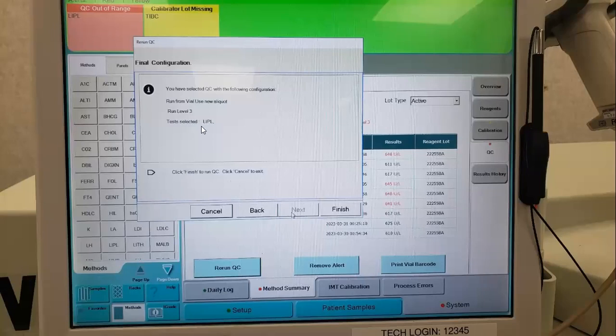And there's a couple different things that we're going to do and wait for. So if the QC is out of range the first time, we're just going to rerun it. The second time, we're going to look and see how many tests are left on the flex pack. And that is what we did earlier when we went down here, setup, and then it will be reagents, and then we will click up at the top.